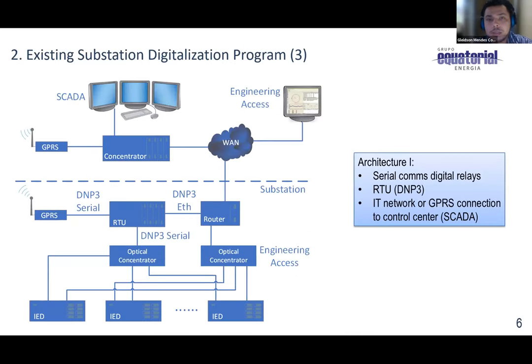And in the beginning of the process of digitalization, we began with an architecture where we had some serial relays, where each serial relay has two ports, port A and port B. The port A of each relay connects to an optical concentrator that communicates with our RTU and then with our SCADA system through the DNP3 serial communication protocol. And all this communication from the substation to the SCADA was done by IT network. We use an IT network until our SCADA that was controlled by the control center.